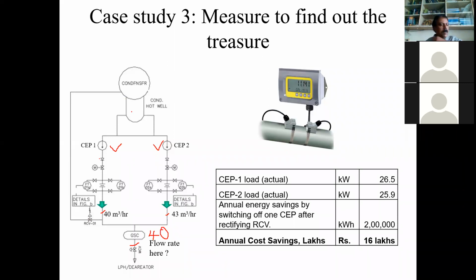It was creating numerous problems, and the company actually started thinking of replacing this pump, thinking that the pump is worn out. The manufacturer also suggested that you should replace the pump. The purchase order was going to be placed. Then we found this was the issue. Then this recirculation valve was rectified, and one pump was switched off. It's a very simple case. Sometimes measurements can help in identifying some stray cases where energy losses take place due to malfunctioning of some of the gadgets.